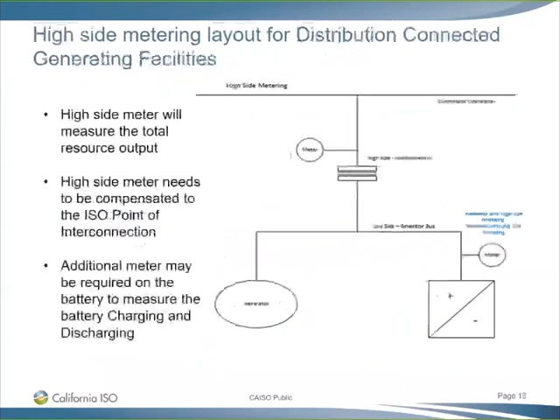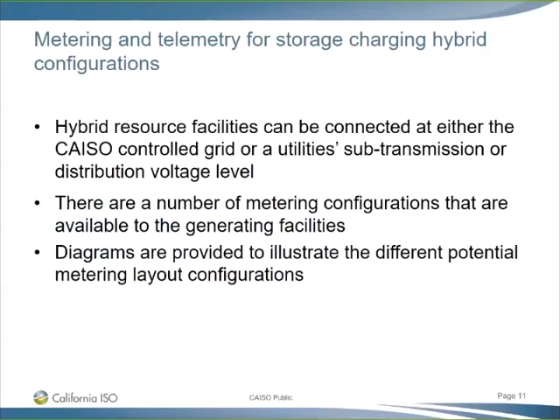On slide 10, I had a quick question to confirm: because it's a public project we don't need the ITC, and we intend to charge from the grid. Our main charging will of course be through the DC coupled PV, but at this point we're targeting participation in the ancillary services market. That could change, but currently that's our plan, so in that market we'd be charging from the grid as well. I want to confirm, because of how the bullet was worded here—no negative generation can occur—that we wouldn't be precluded from charging from the grid.